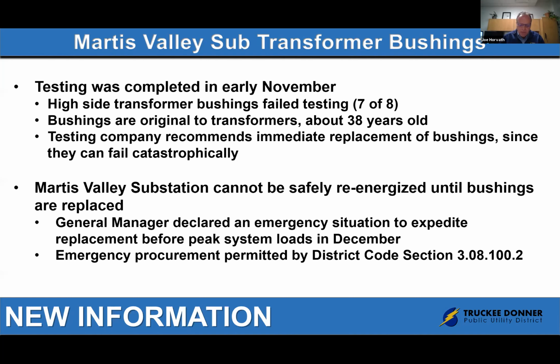Staff strongly believes, based on this knowledge and the recommendations from our testing company, that Martis Valley substation cannot be safely re-energized until these bushings are replaced. Therefore, the general manager declared an emergency situation to expedite the procurement of these bushings before peak system loads occur in December. This emergency procurement action is permitted by District Code Section 3.08.100.2.